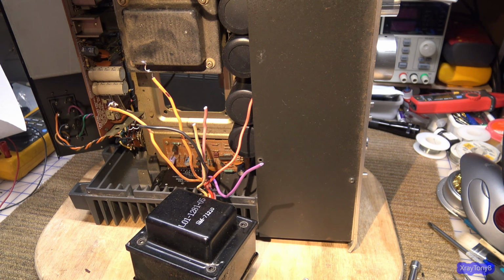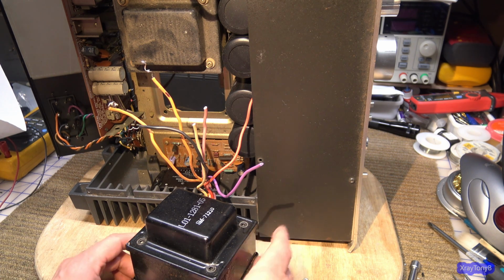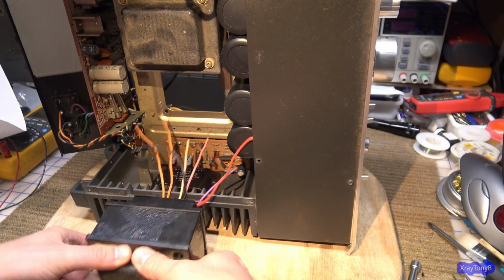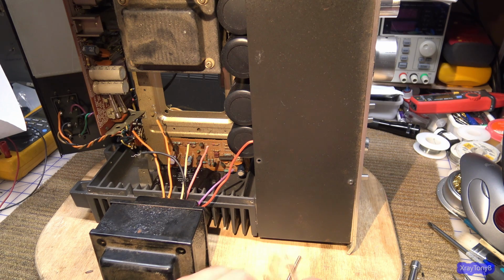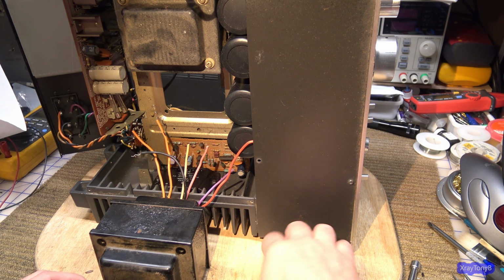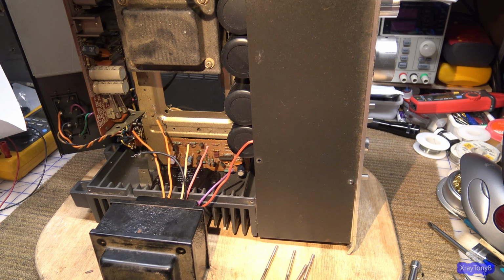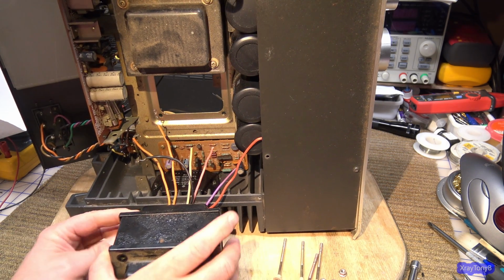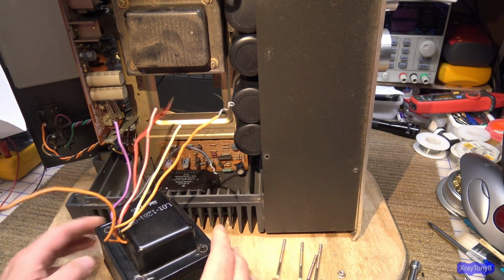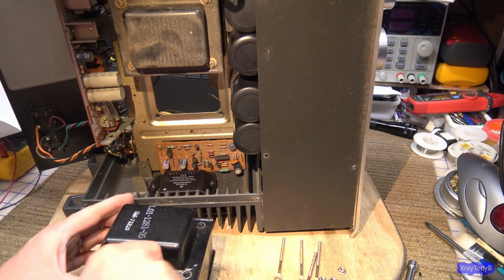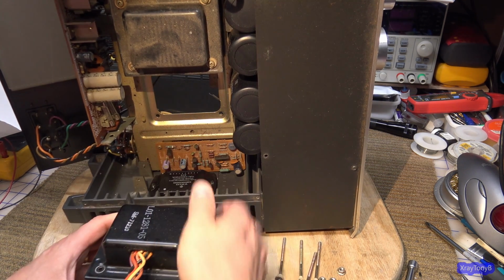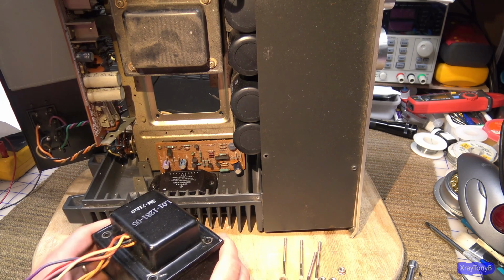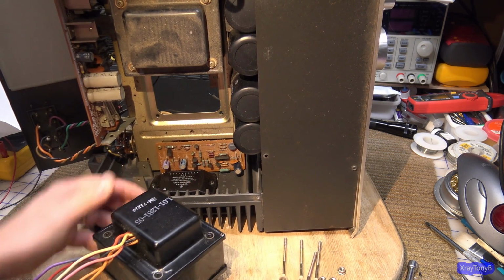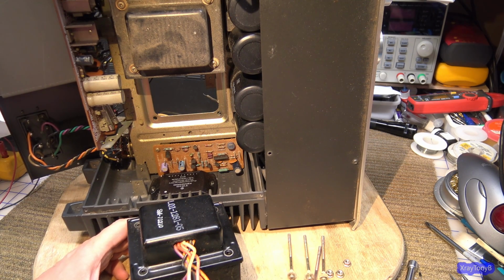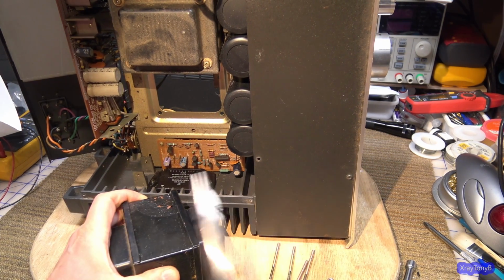And what happens is if that varnish breaks down, it'll basically cause those plates to short out against one another, and it will make the transformer much less efficient. The transformer, during operation, will actually run much hotter. So if you have a transformer that's running really, really hot, even though the circuit is not drawing a lot of current, it may be that the laminations of your core are shorting out. And that definitely can happen to an old transformer, so you have to kind of watch out for that. I'm hoping that's not the problem with this one.